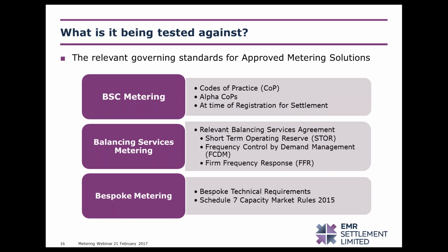So as I mentioned earlier, your metering solutions will be measured against the relevant governing standards for that solution. Where you have BSC metering installed, it will be measured against the relevant codes of practice. These could be the numerical codes of practice or the alpha codes of practice, and it will be determined by the date at which your metering solution was installed. For balancing services metering, it will be measured against the relevant agreement you have with the National Grid, so this could be STOR, FCDM, or FFR. If you have bespoke metering installed, you'll need to refer to the technical requirements which are explained in Schedule 7 of the Capacity Market Rules.